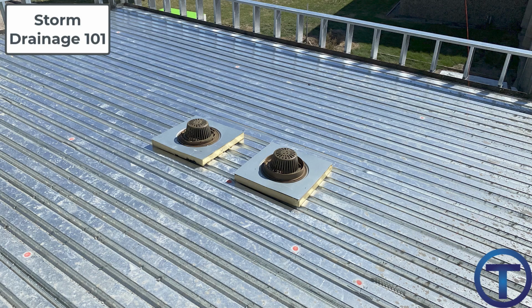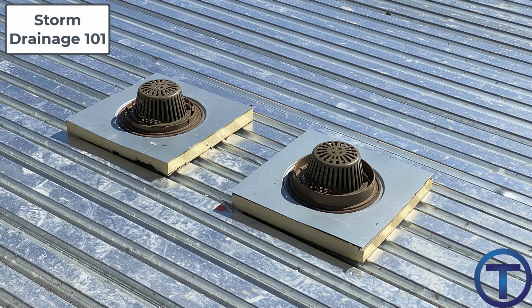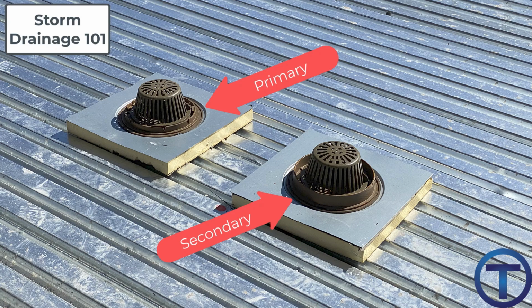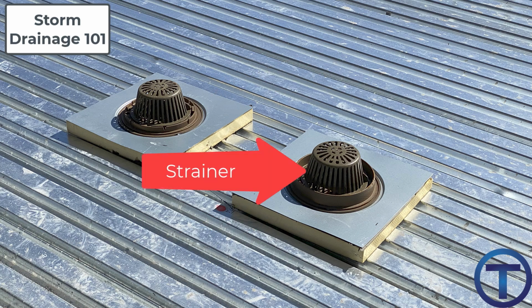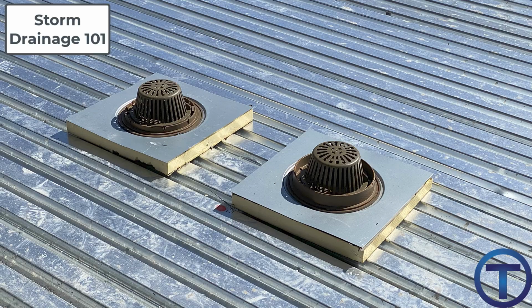Let's have a quick look at roof drain assemblies. How does the roof drain actually connect? On top of the roof, you're going to have a bowl. This is the actual roof drain. And on top of that, it's going to have a ring that will adjust the height to which the water can come into the bowl, and also a basket strainer that's going to keep leaves, branches, and other junk that lands on the roof from going down the drain. This is the top side.